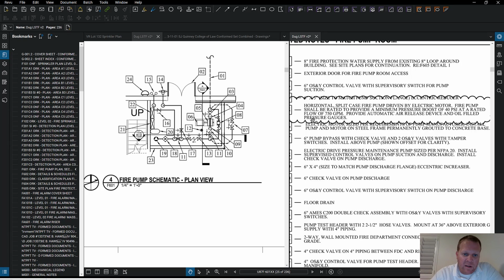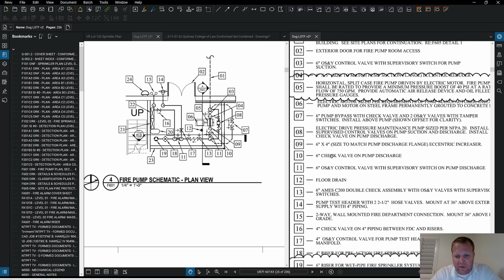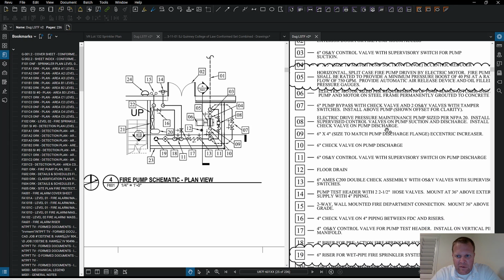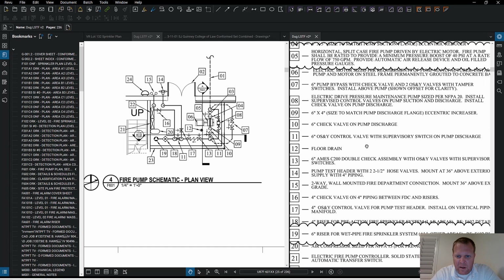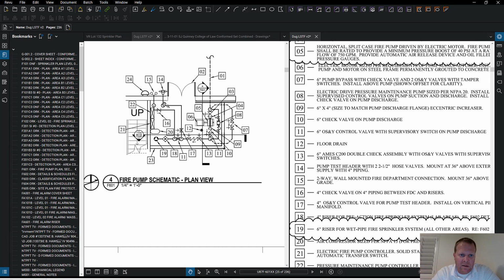Pretty cool. And then we could read all this stuff, but I don't think it's worthwhile to spend a ton of time. Let's just read through a few of these. We've got check valve, pressure maintenance pump. Let's see. Pump test header number 14. I might show a little what's that about. So in order to test this pump to see how it's working, they'll isolate the valves so that they're not pressurizing the pipe downstream of this test header, and they'll be able to shoot water out of this and be able to measure how much water and see if it's doing 700 GPM.